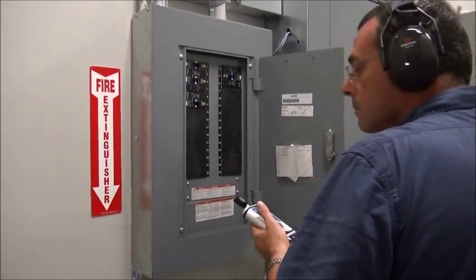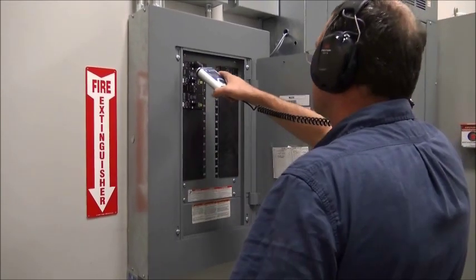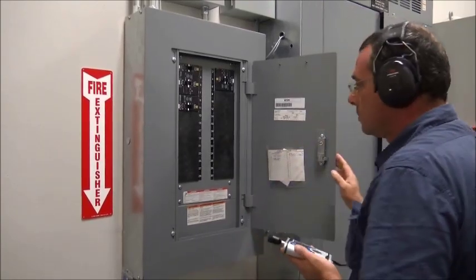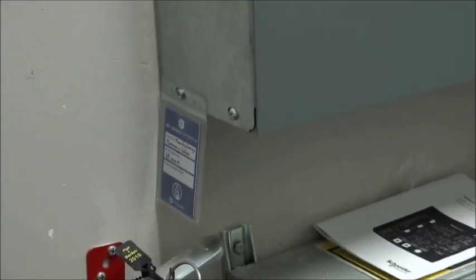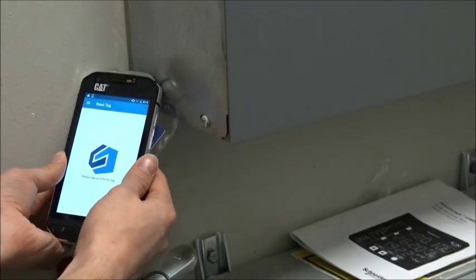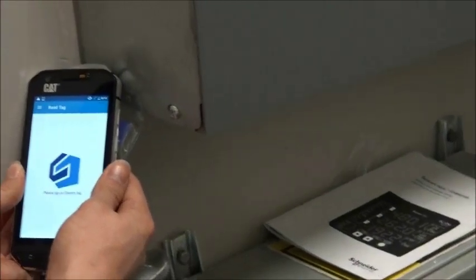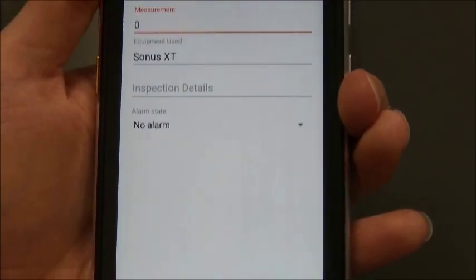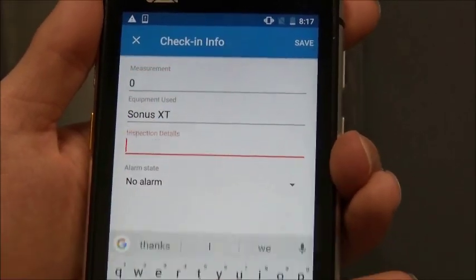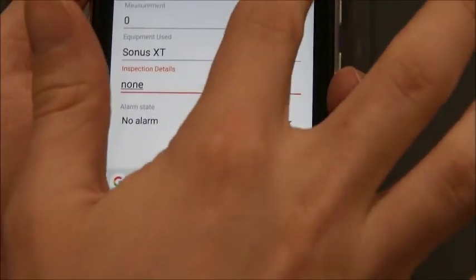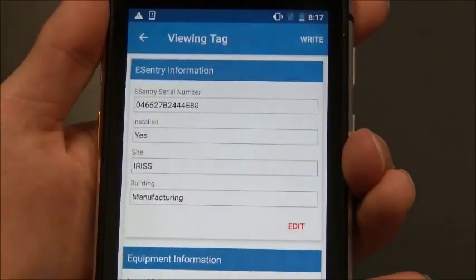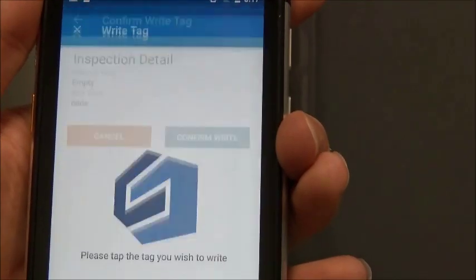Using the Sonus XT handheld ultrasound tester, he begins the inspection by opening panel H1's door and scanning and listening for any unusual ultrasound emanating from the enclosure. To begin recording data to the tag, he taps it to read current data on the tag into the eSentry Connect app. Here he sees when and by whom the previous inspection was performed along with the data they recorded. He records his findings and notes into the app and writes that information to the tag with a few finger taps.